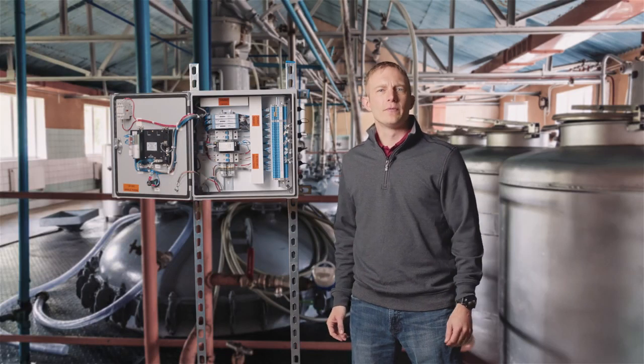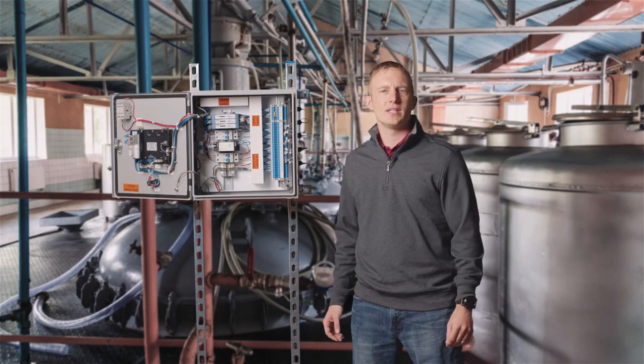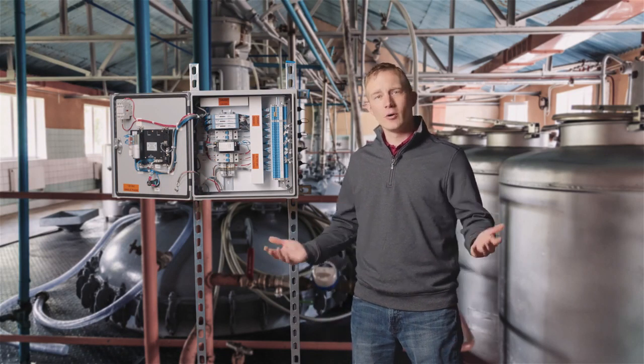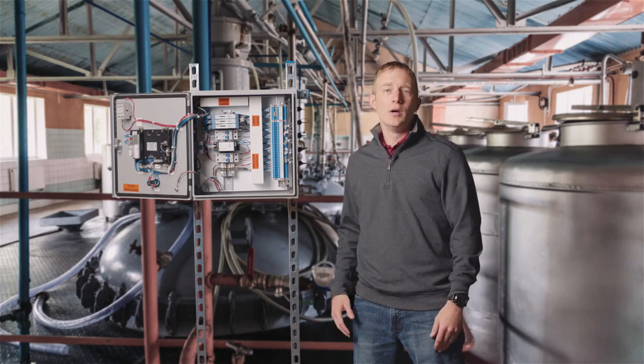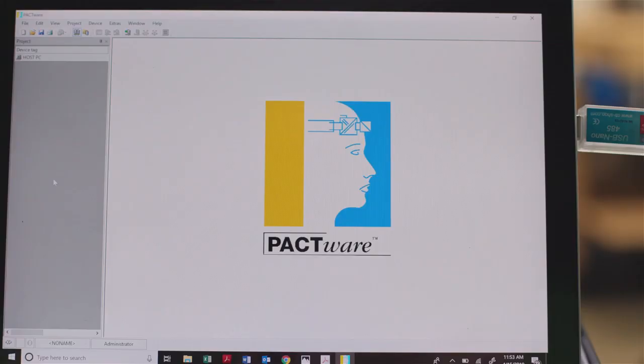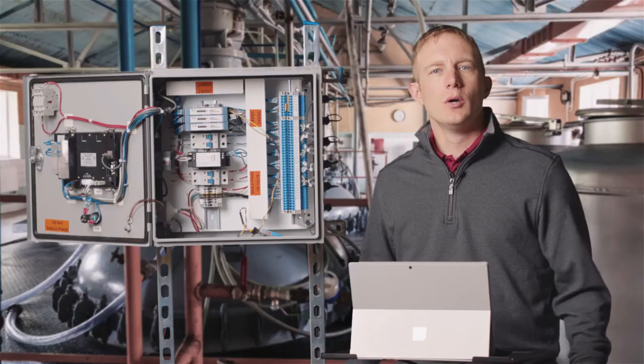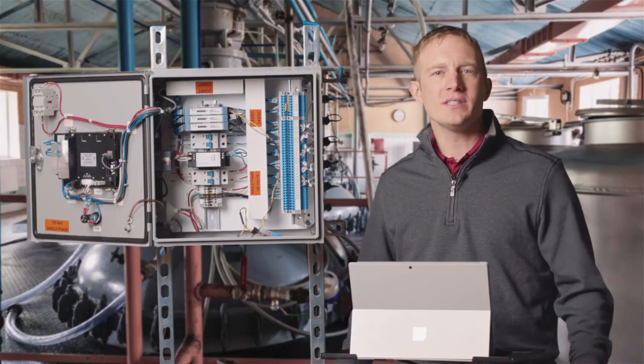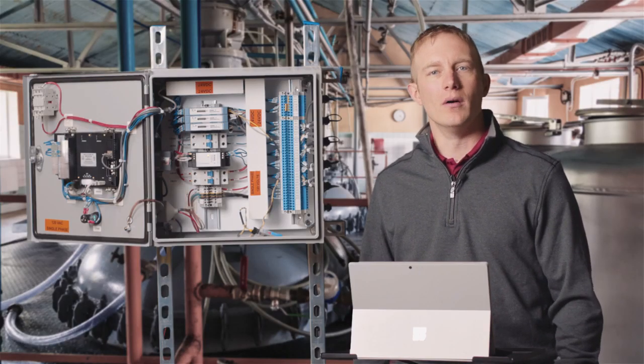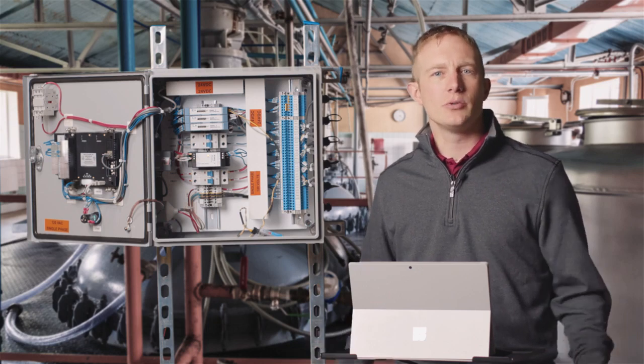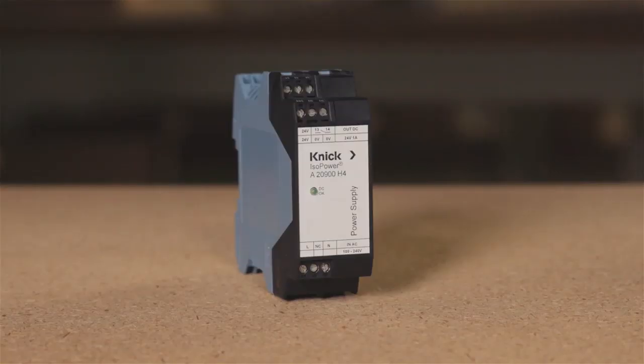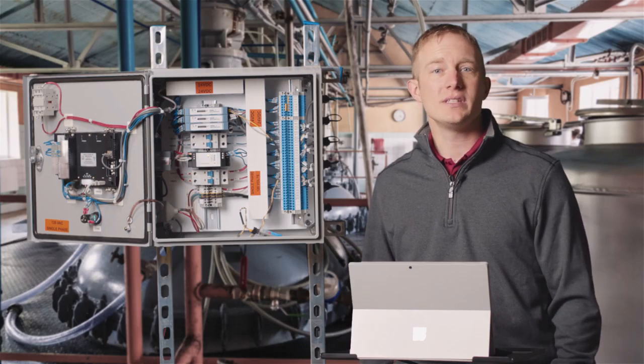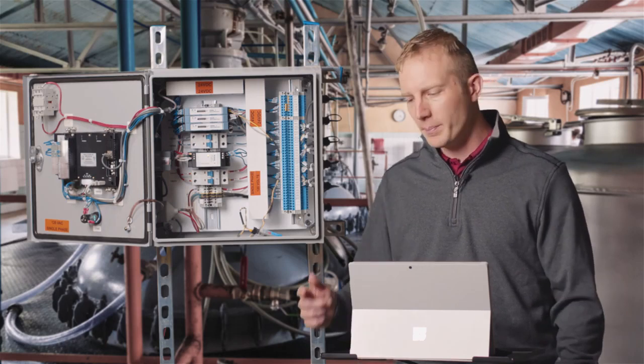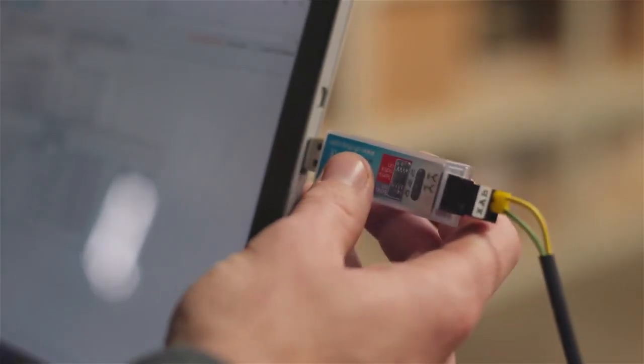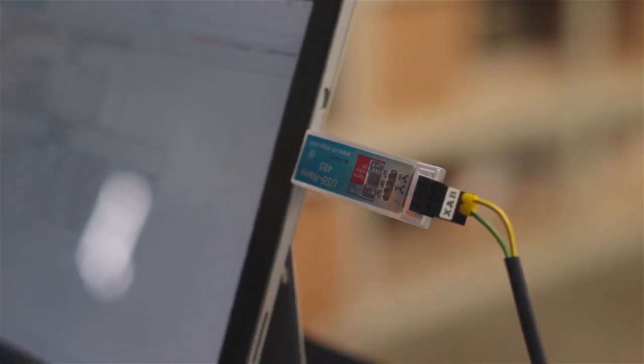This allows us to perform a calibration on our connected sensor directly through the control system, HMI, or the device type manager, which we'll be utilizing today. We'll start by ensuring that at least one sensor is connected to our MemoRail. Our MemoRail should be connected to a 24-volt DC power supply, and our Modbus RTU terminals should be connected to our PC via an RS-485 to USB adapter.